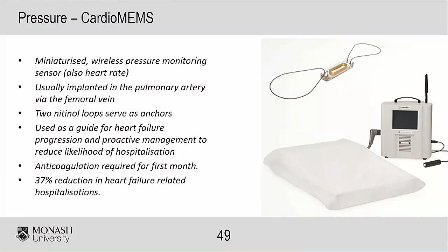The way it works, it uses microelectromechanical systems, or MEMS. It has a coil and a capacitor on a tiny little electric circuit in it, and this sort of resonates or vibrates essentially at a specific frequency, right? When there's pressure applied to a membrane in there, or a pressure sensitive surface, it changes the frequency that coil and capacitor vibrate at. Now, what makes them vibrate is an electromagnetic coupling via an external antenna, which powers the device via RF, radio frequency, and continuously measures the resonant frequency. So basically, it has no power at all in it, sits inside the artery there.